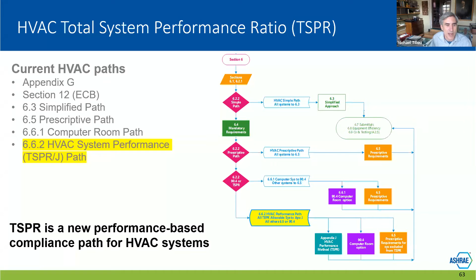As Dick explained, TSPR is a new optional performance pathway in Section 6 for HVAC systems. It sits there as an alternative to the prescriptive path. Next slide. And really the idea of this new performance-based HVAC path is similar to the Appendix C performance path that has been in 90.1 for a long time for the building envelope. So the intent is to allow a project to look at the HVAC system as a complete system, not as individual components the way the prescriptive path does. So you model your proposed HVAC system, and it gets compared to the performance of a good system, good in quotes, for your building type.